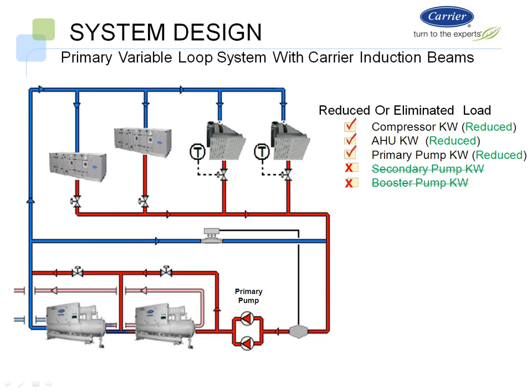Correct, because a lot of times you might even be required to use a dual energy recovery, which gets very, very costly, and it also limits you to potentially one or two vendors on those types of primary air systems. Where when you start introducing this induction beam, not only do your air handlers become smaller because you're doing less, you're just handling the outdoor air, let's call it neutral air at that point, but the beams can now do some of the latent as well, so the air handlers might even be reduced further, and it becomes more of a common air handler. And any air handler out there with a certain amount of cooling coil rows can handle 100% outside air.